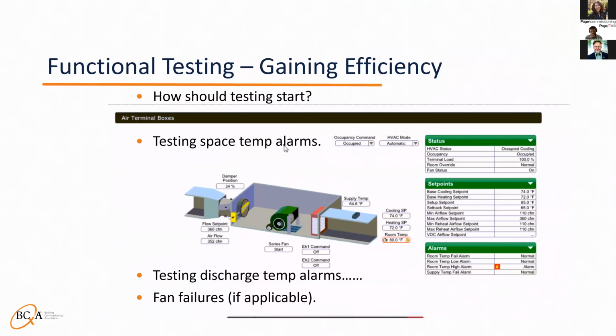So how should testing start? This is obviously the CxP's preference, but we feel like starting with safeties and alarms is best, usually because it verifies that any full capacity testing will not hurt the system. Now, for most terminal unit safeties do not apply, but nevertheless, it's a good habit to have.